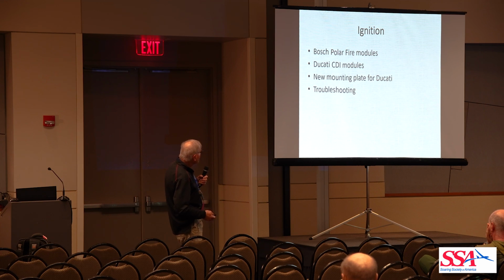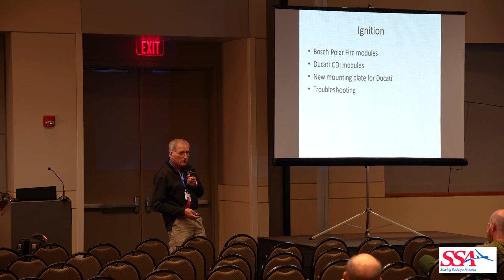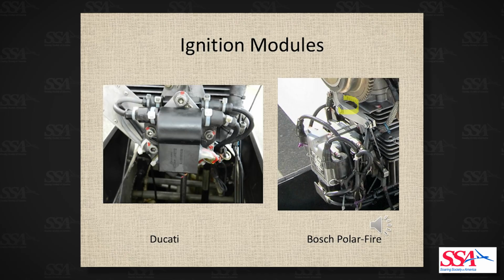Then there's the ignition issues. The original Bosch Polar Fire modules went out of production, and DG switched to the Ducati modules, which required a new mounting plate for them. A lot of problems with these ignition modules are wire breakage due to vibration.